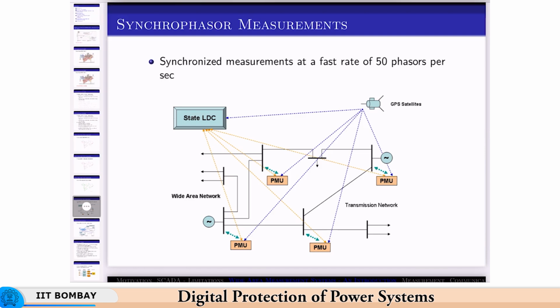Now the synchrophasor measurement transmissions are at the fast rate of 50 phasors per second, so 50 hertz. And the slowest is about 10 hertz. So you can see that in India we are using 1 phasor per 2 cycles, so that is 25 hertz. The IEEE standard, we will see the rates a bit later, also allows for 2 phasors every cycle. So 100 hertz for a 50 hertz system and 120 hertz for a 60 hertz system.